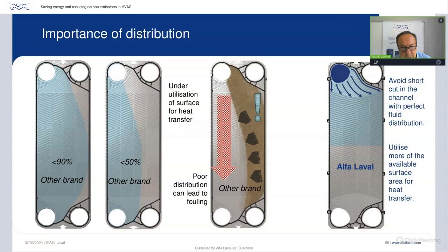So how does the distribution pattern help us to save energy? If you look at another brand, not Alfa Laval, on the left, you can see if they have a poor distribution pattern, as you see here, then we will get dead spots and the fluid not reaching all the extremities of a channel. There are local brands and brands that are manufactured in China, like copycat units and such, which are actually utilizing less than 50% of the available surface because they don't have a very good distribution pattern.